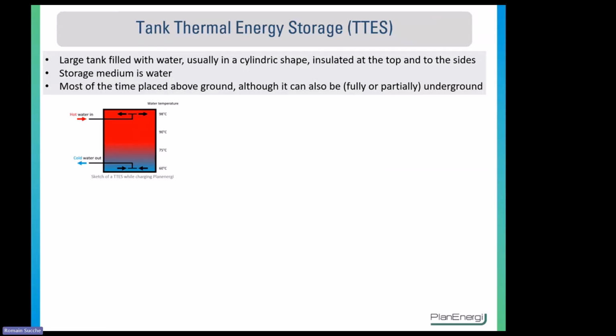So as I said, I'm going to start. I'm going to present the four different main technologies, starting with the tank thermal energy storage, which is essentially a cylinder of steel filled up with water, treated water, and which is insulated from the top and the sides. And you can see a sketch here where basically there are two, or at least two, but also sometimes more diffusers to be able to charge and discharge the storage system. And the heat is stratified, so you would discharge. I mean, in this case, it's a sketch of the charging process where you would extract water from the bottom and put hot water on the top.